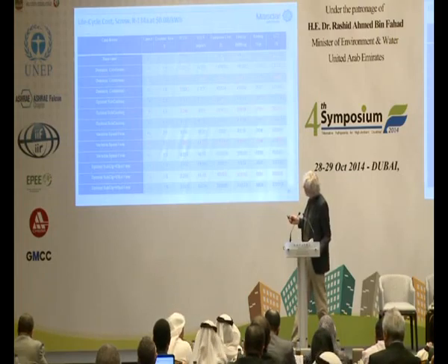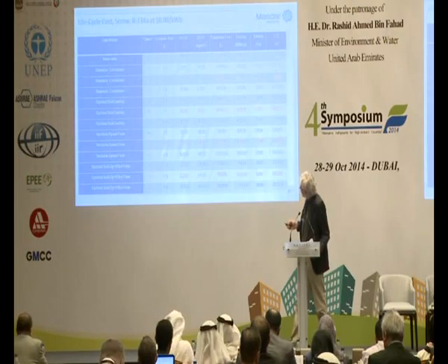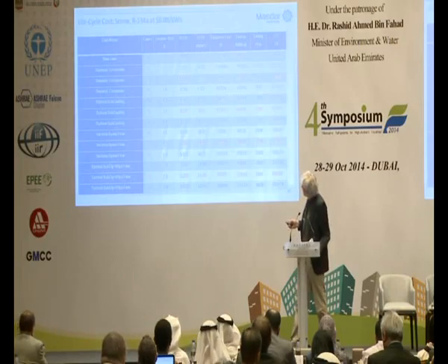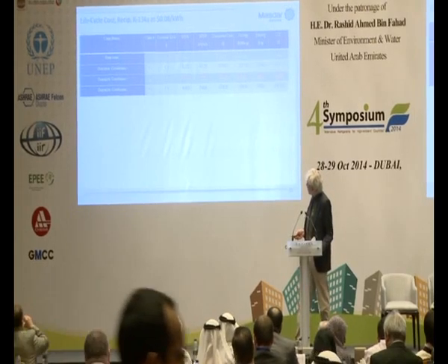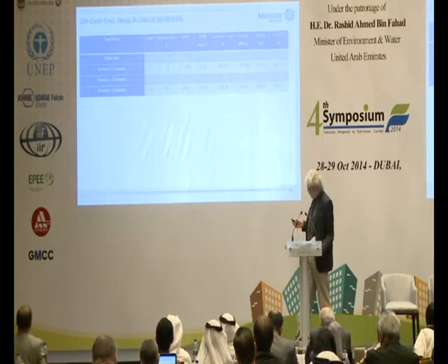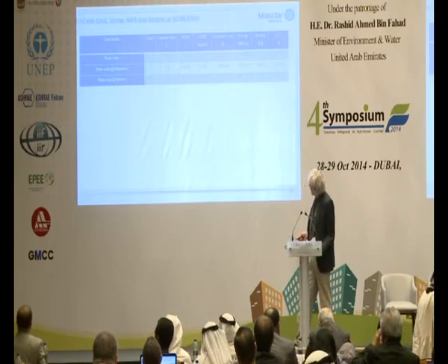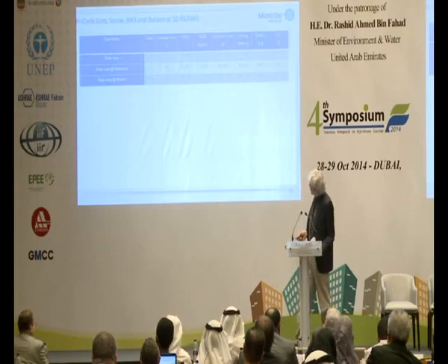Just to quickly read off some numbers, we have SEER improvements of about 20% for just the oversized condenser, further improvements for optimal subcooling of about, I think it's 10%, and variable speed fans take us further. But the real improvements are when we go from the screw compressor to the reciprocating compressor, where we get SEER improvements of up to about 70%. Finally, we did just a few runs recently with different refrigerants, one of them being butane, showing SEER improvement of just over 1%, and ammonia showing SEER improvement of over 13%.